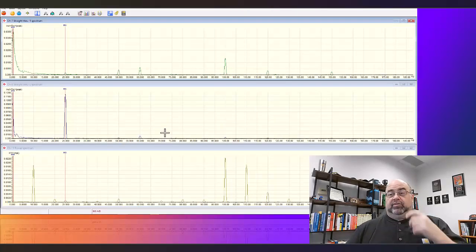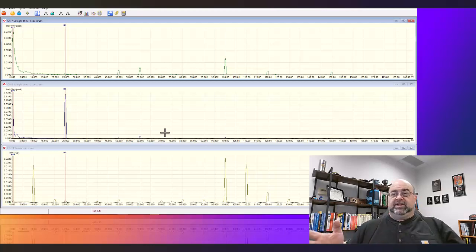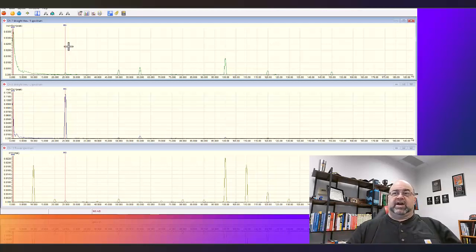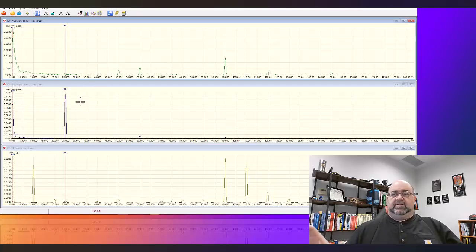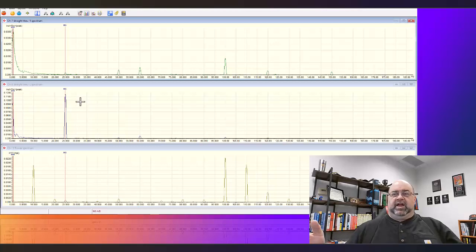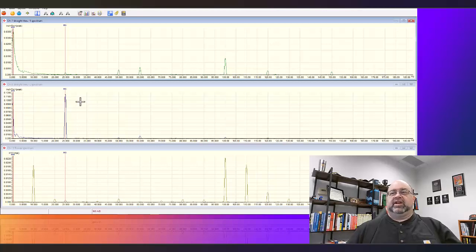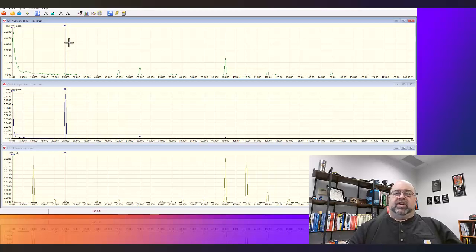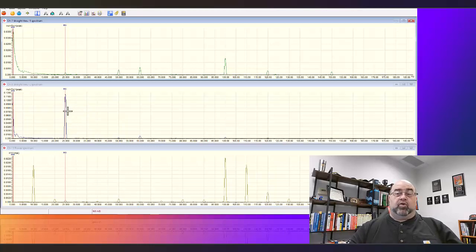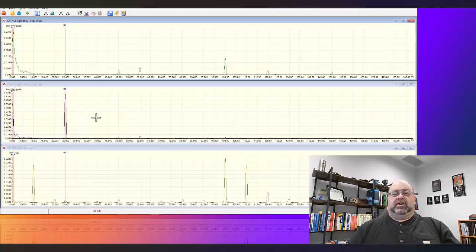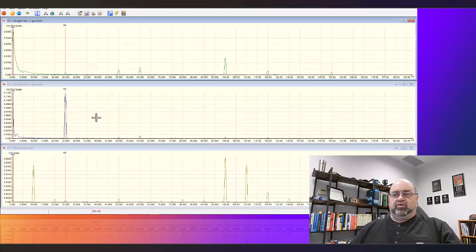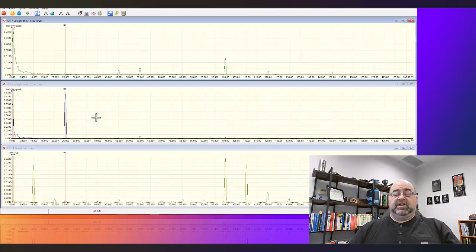So here's the data we got with the top one being drive-end data. By the way the locations in that image of the vibration accelerometers is not accurate for the study we're doing. So the top one is our vertical, this one here is horizontal. The motor is bolted to a mass larger than its weight. The weight for the motor is 10 kilograms per the catalog.